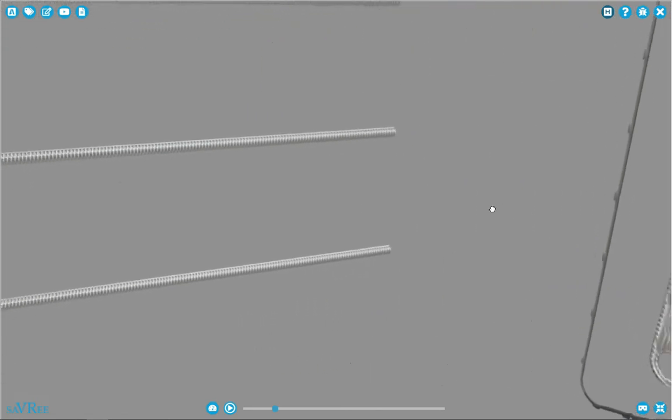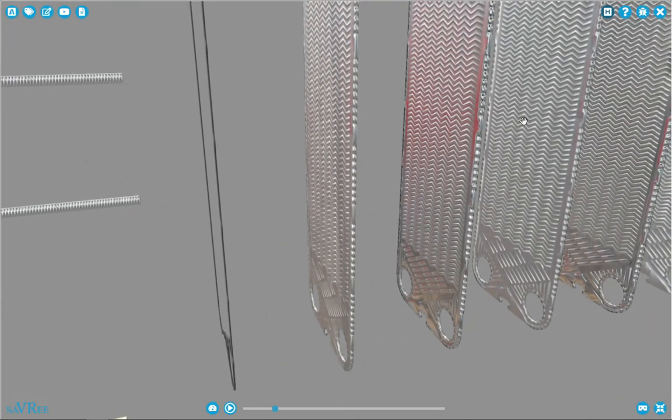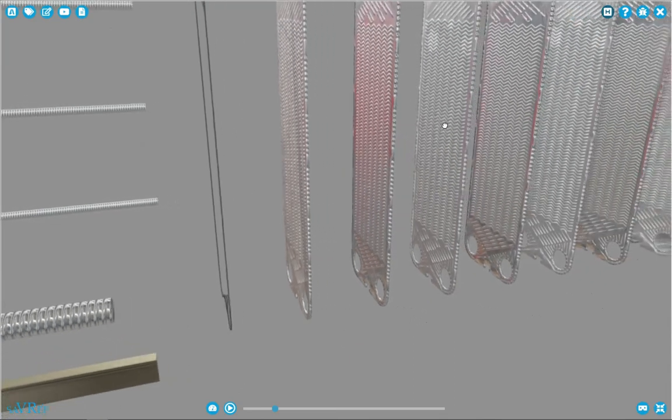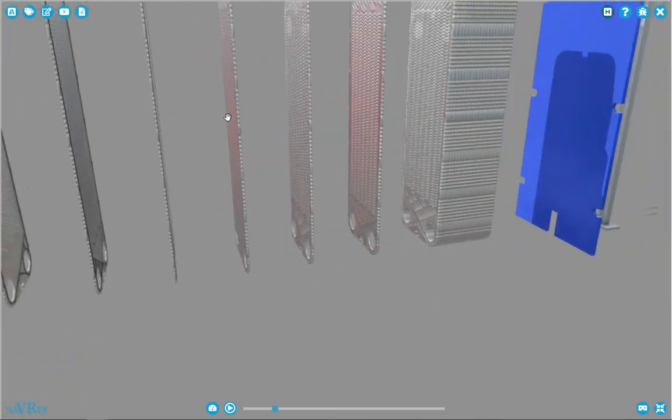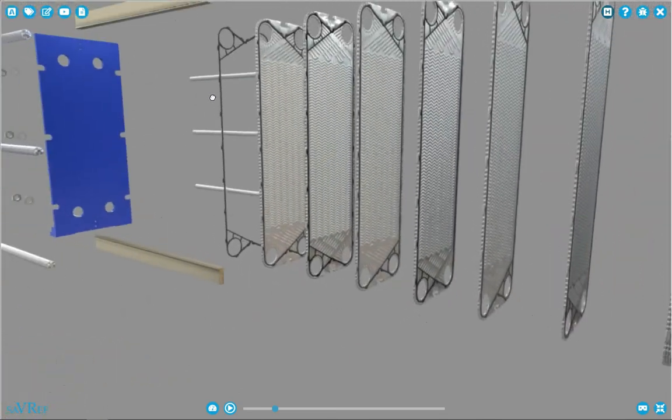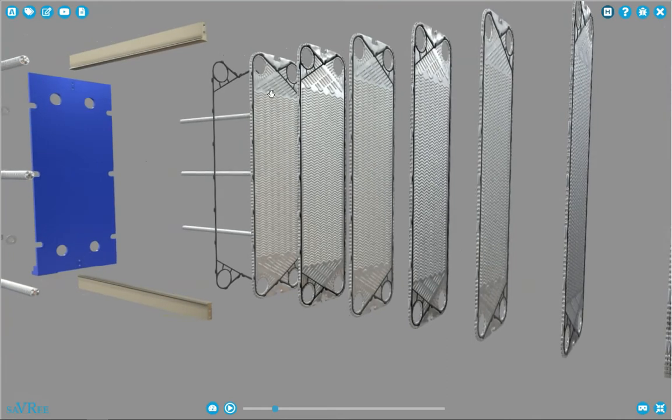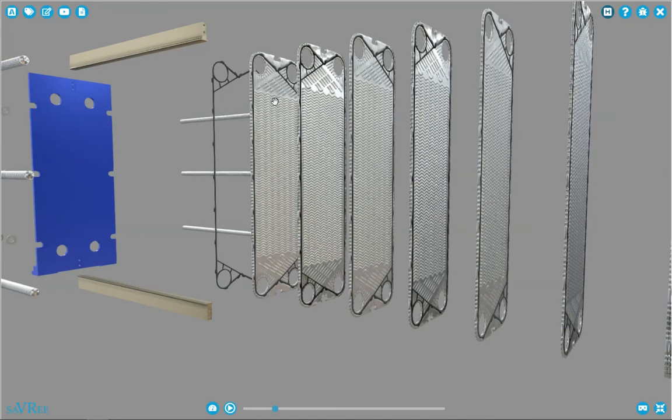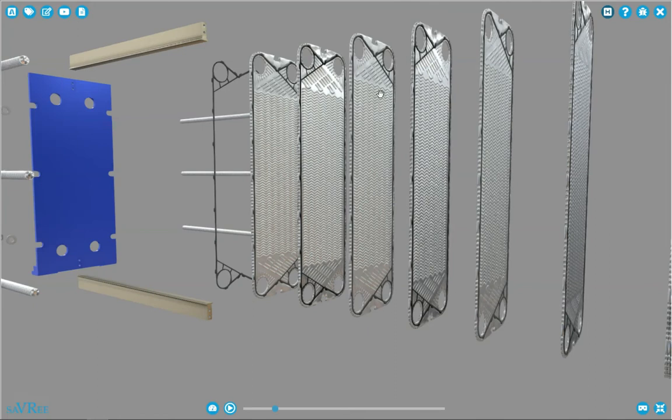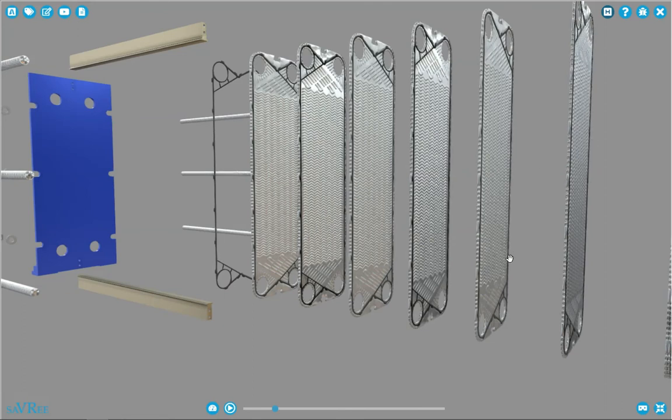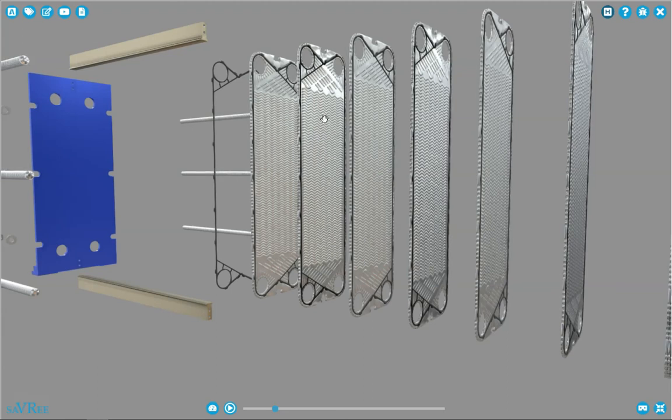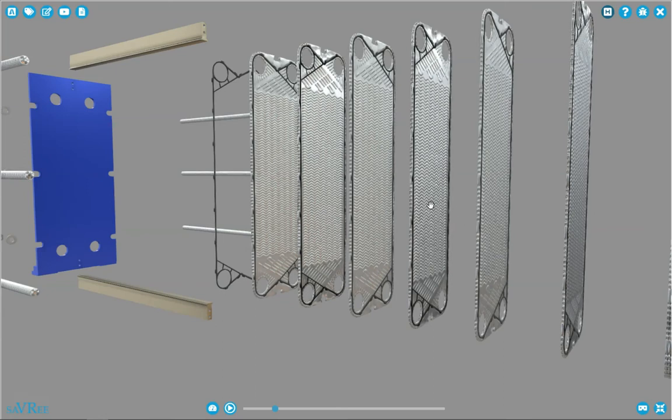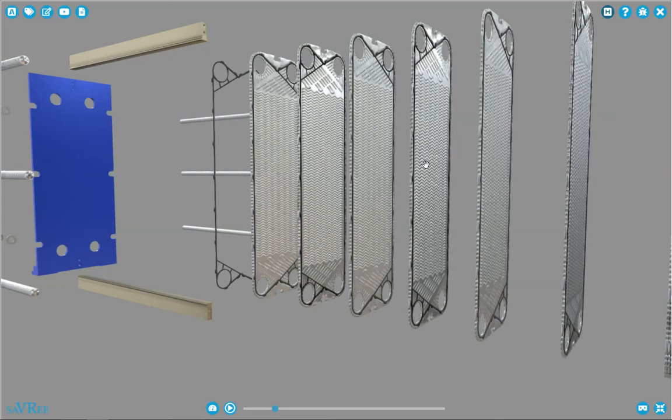So if we look at what it looks like on the back, on the back side of these plates, what we can see is that we have those gaskets, and so there's one in between each plate. And in this case, the gasket alternates. So we start and we have this side that's able to flow, and on this side we're able to flow then to the left, to the right, to the left, to the right, and so on. And so we keep going back and forth where we have one fluid pathway, then the alternate, then the other, then the other.